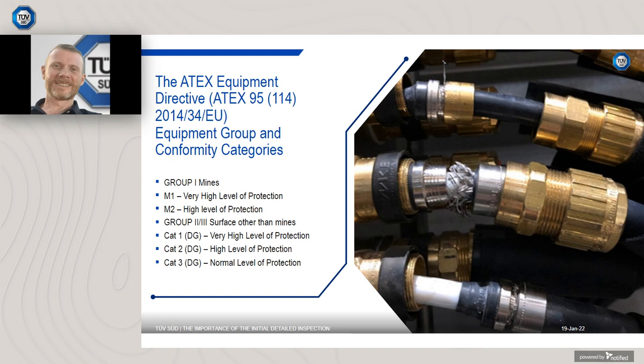The ATEX Equipment Directive, the equipment groups and conformity categories. The three equipment groups are broken into 5 categories. The categories are the level of EX protection required. Equipment protection systems conformity assessment details the level of protection. Very high, 2 independent protection methods, safe with 2 faults. High, safe with 1 fault. And normal, suitable for normal operation.